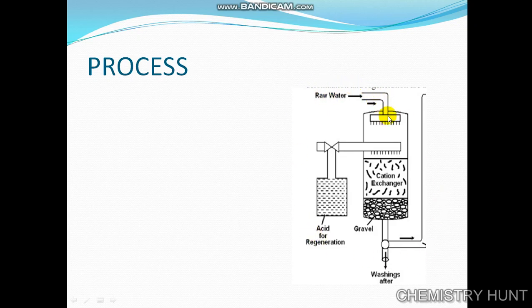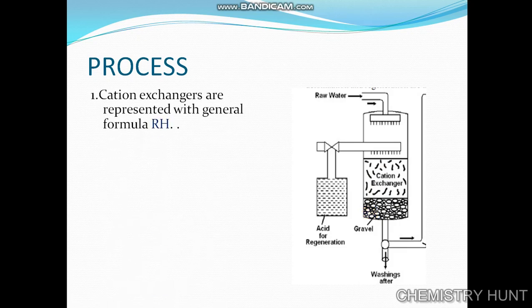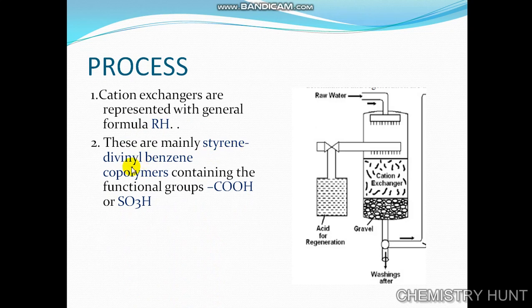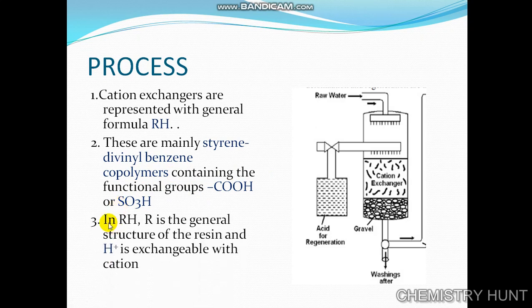This diagram is just for understanding and not to be drawn. The raw water is passed into the cation exchanger where all the cations are retained and it gives an equivalent amount of hydrogen ions. Cation exchangers are represented with the general formula RH. These are mainly styrene-divinyl benzene copolymer containing the functional group carboxylation or sulfonation. In RH, R is the general structure of the resin — the styrene-divinyl benzene copolymer — and hydrogen ion is the exchangeable cation.